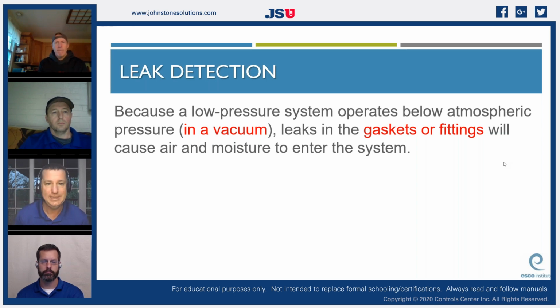On a type 3, it's just the opposite. On our entire low side of our system, it's continually operating in a vacuum. And even on our high side, we may not have much pressure at all. Our low side is constantly in a vacuum. So if there is a leak on that system, we have to completely change our mentality, because I cannot use a leak detector to find a refrigerant leak on a type 3 system. I can use an ultrasonic that's listening.